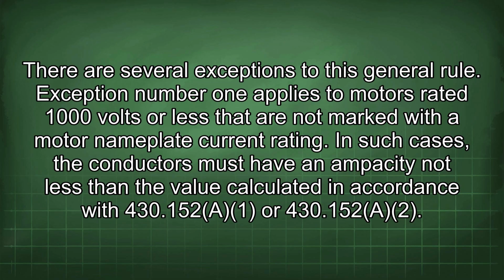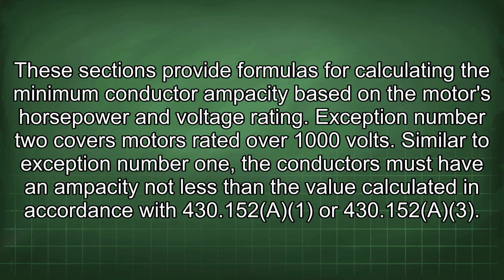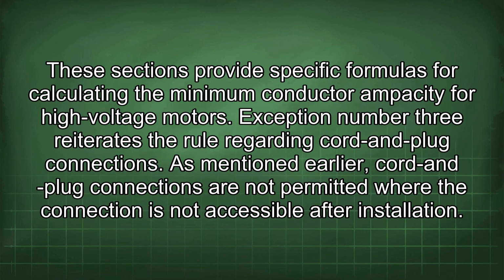Exception number 1 applies to motors rated 1000 volts or less that are not marked with a motor nameplate current rating. In such cases, the conductors must have an ampacity not less than the value calculated in accordance with 430.152(A)(1) or 430.152(A)(2). These sections provide formulas for calculating the minimum conductor ampacity based on the motor's horsepower and voltage rating. Exception number 2 covers motors rated over 1000 volts. Similar to exception number 1, the conductors must have an ampacity not less than the value calculated in accordance with 430.152(A)(1) or 430.152(A)(3). These sections provide specific formulas for calculating the minimum conductor ampacity for high-voltage motors.